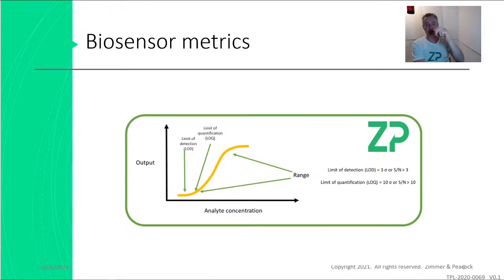and that's what makes it a really interesting, demanding thing, because you can do all the data sheets you like, and we do them in buffer. But of course, people are not running biosensors in buffers. They're running them in urine. They're running them in blood. They're running them on the breath vapor, as we do. Running them in plasma, running them in serum. So the question about, do you have a data sheet for a biosensor? The answer is, we have information about the sensor, but the best way of understanding the performance of a sensor in a particular application, unfortunately, is to actually run it.